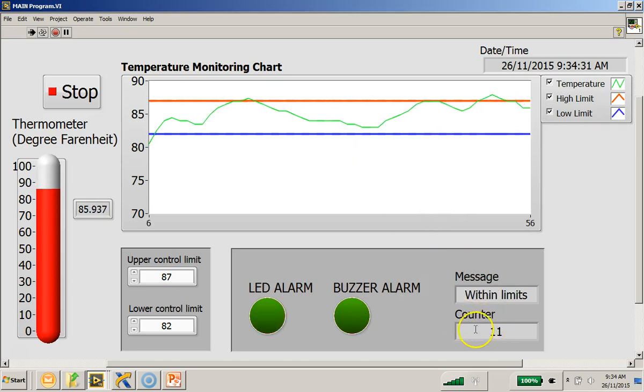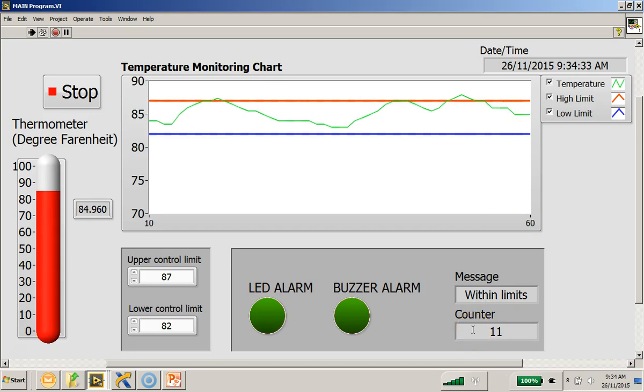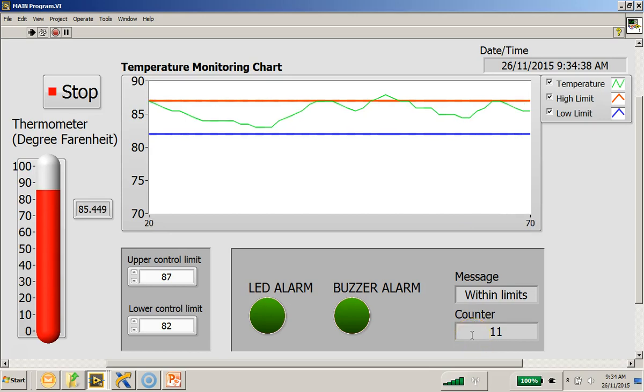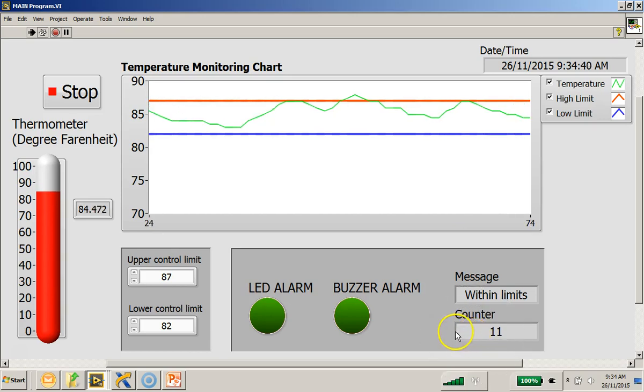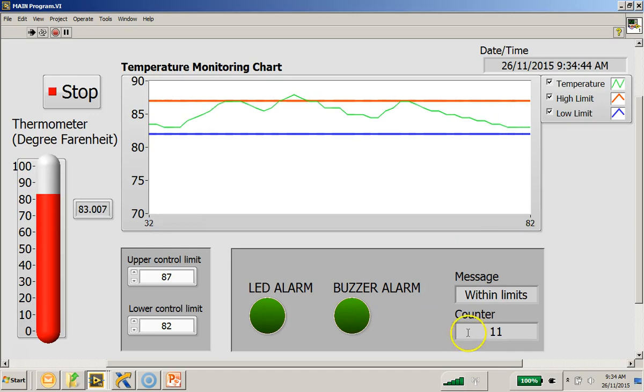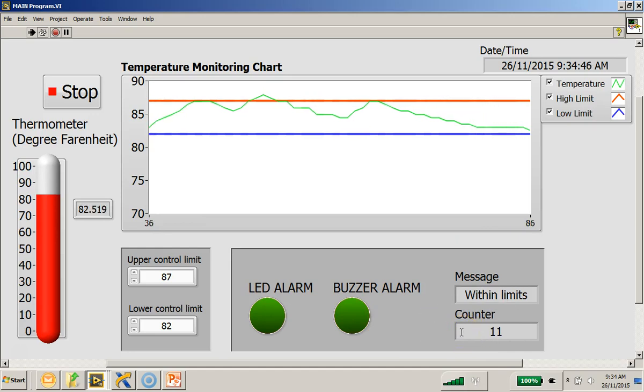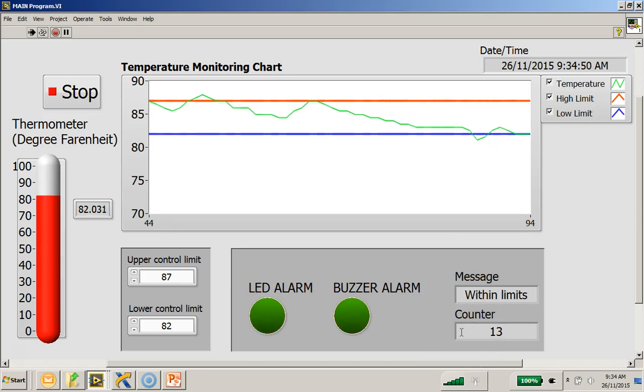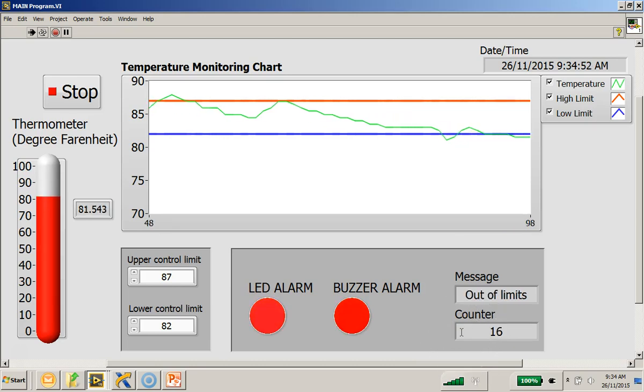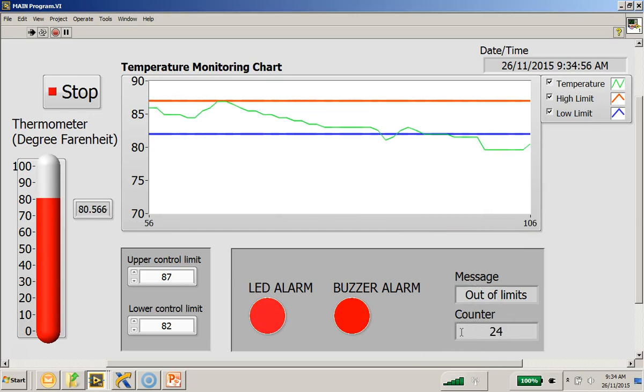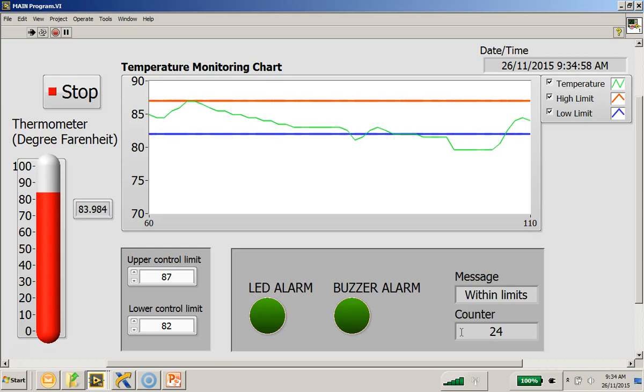And when it is not within the limits, the counter will also be incremented once the alarm is activated. You can see in a very short time that the counter is being incremented for the fact that the temperature reading is not within the limits.